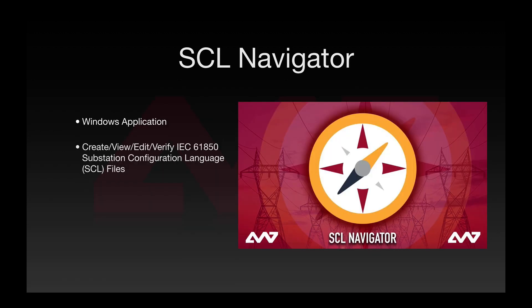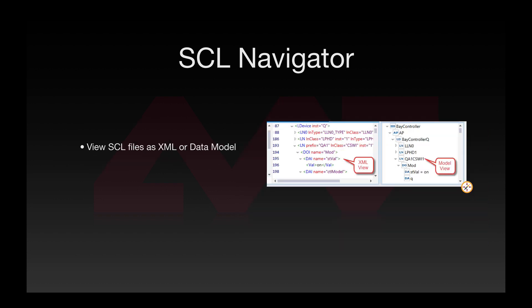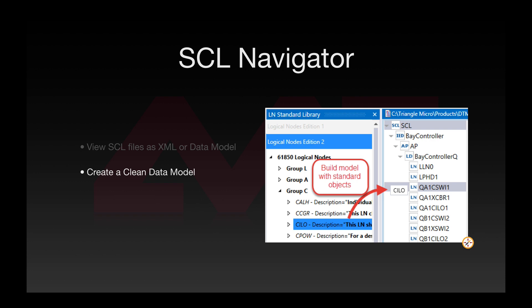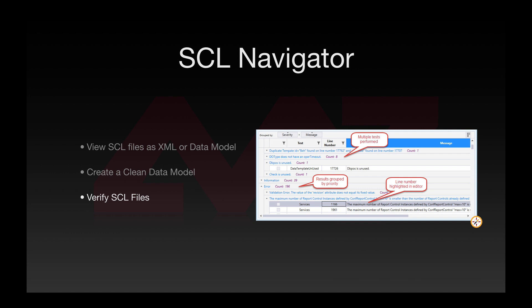SCL Navigator is a Windows application that supports creating, viewing, editing, and verifying IEC-61850 substation configuration language, or SCL, files. With SCL Navigator, you can view the SCL file in either the raw or native XML format, or as a data model. You can also easily create a clean data model using the built-in models and templates, and verify SCL files to quickly find and correct any issues.